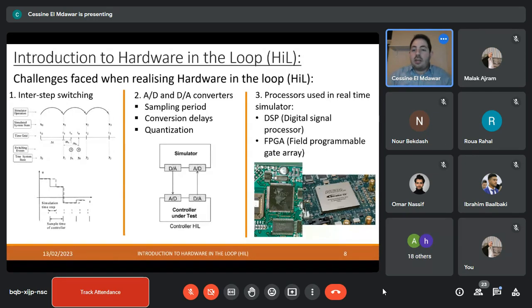However, even if it's more accurate but only responding every 100 milliseconds, a scenario like this can occur: during those 100 milliseconds the controller sends two separate signals, A and B. If the real-time simulator only computes at T1 and T2, it won't be able to see point A, only point B. That means it loses accuracy because it isn't able to compute fast enough.